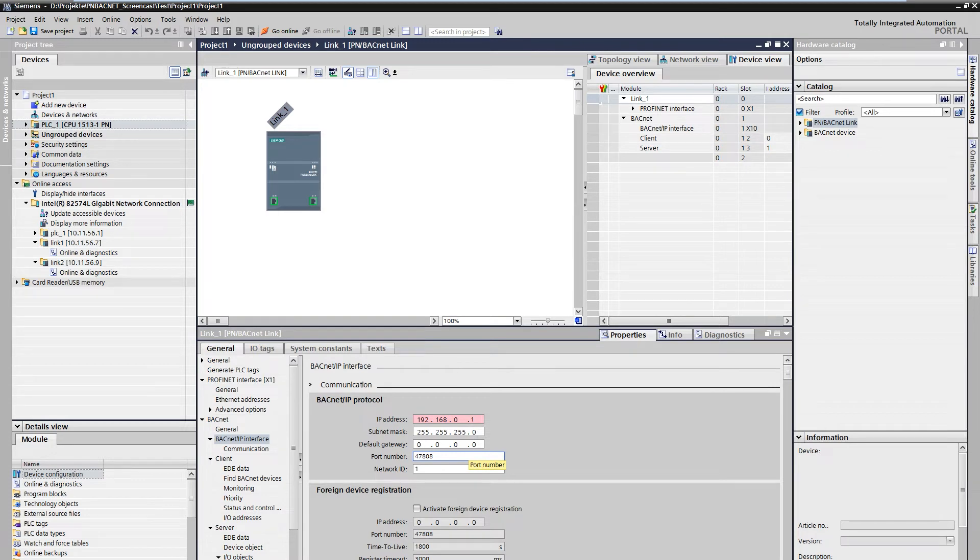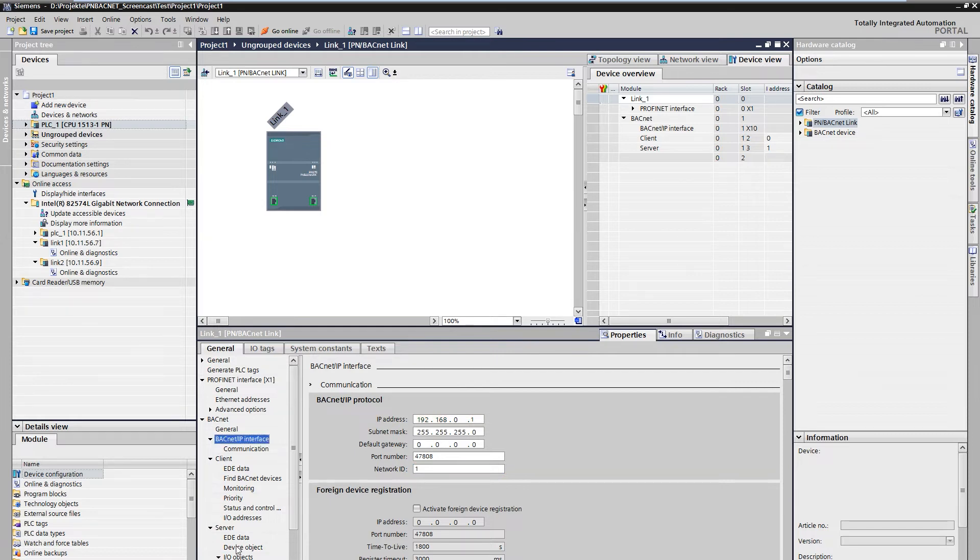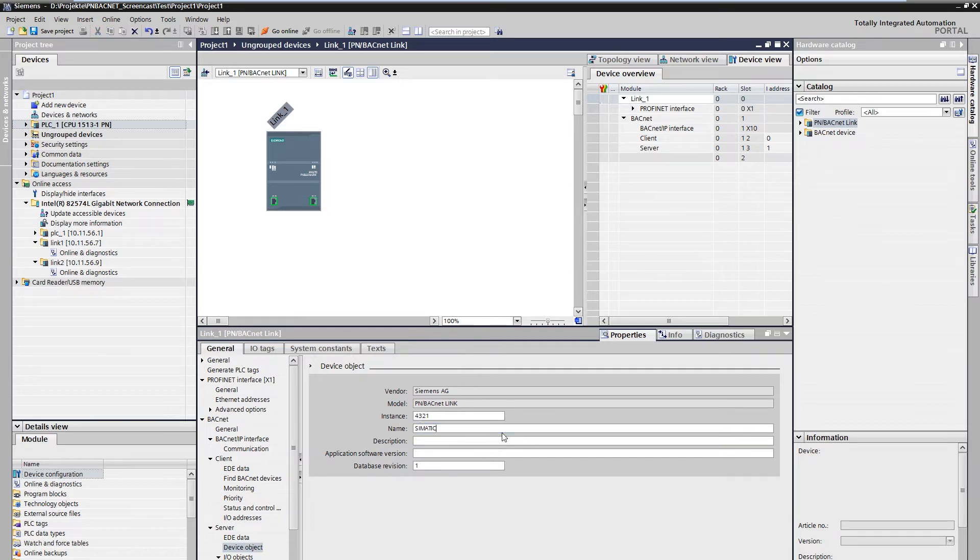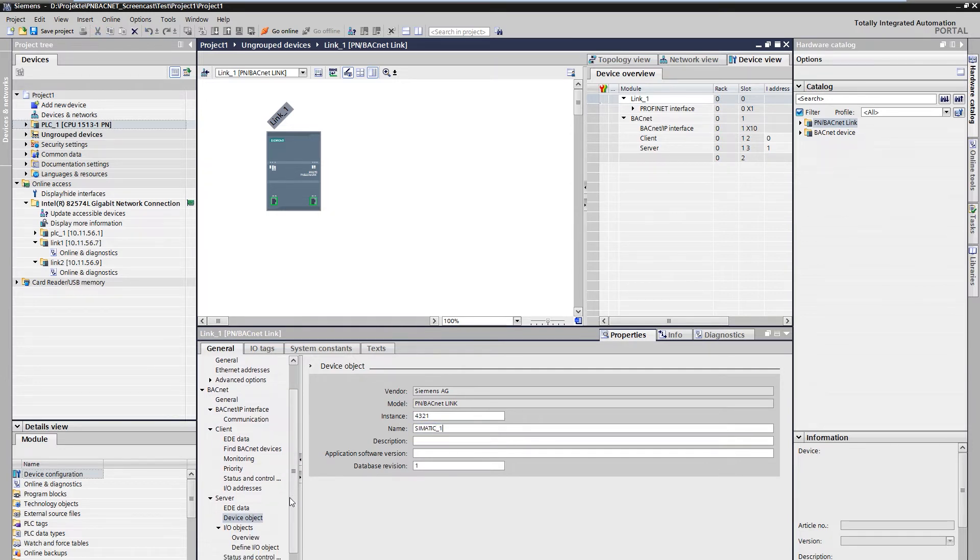To configure the device as a BACnet server, an explicit and unique instance ID as well as a name are assigned in the server properties. With these settings, the device is displayed as an object in the BACnet network.